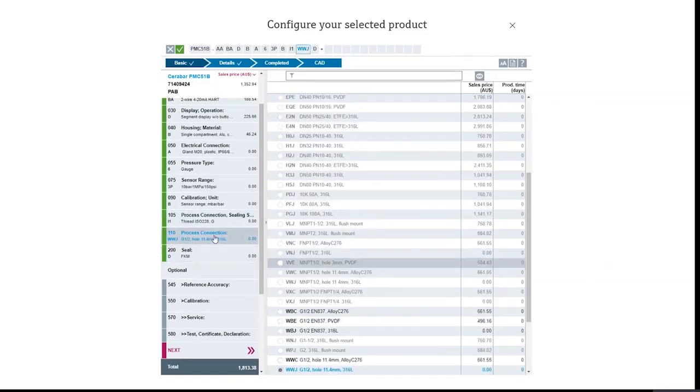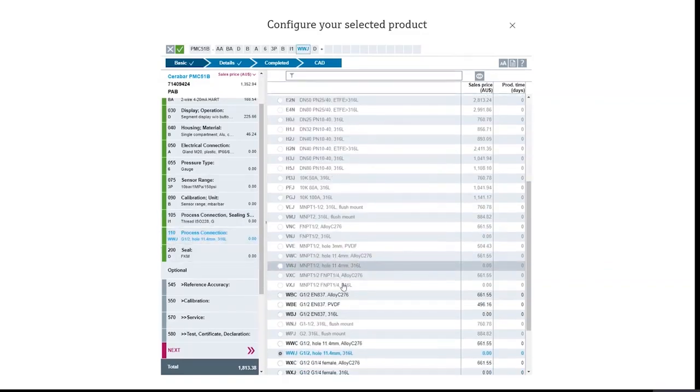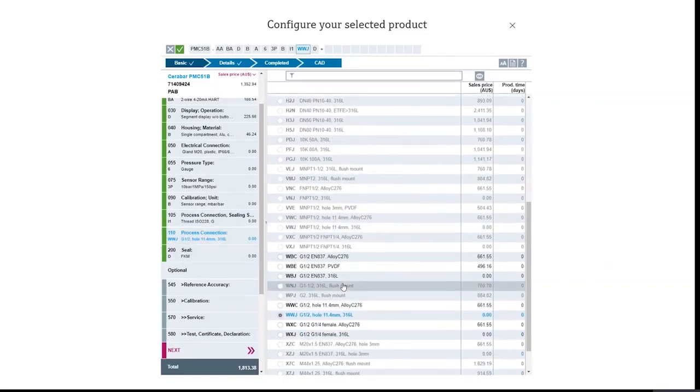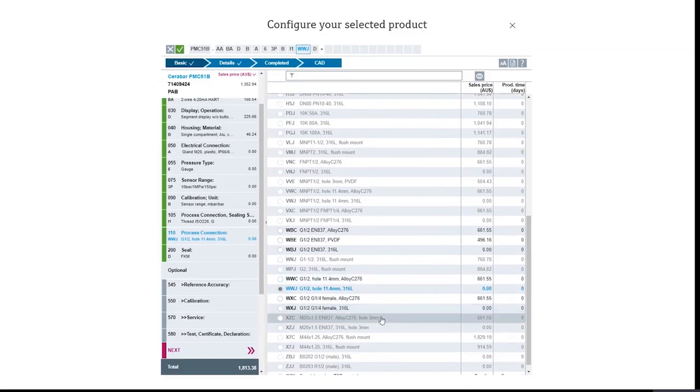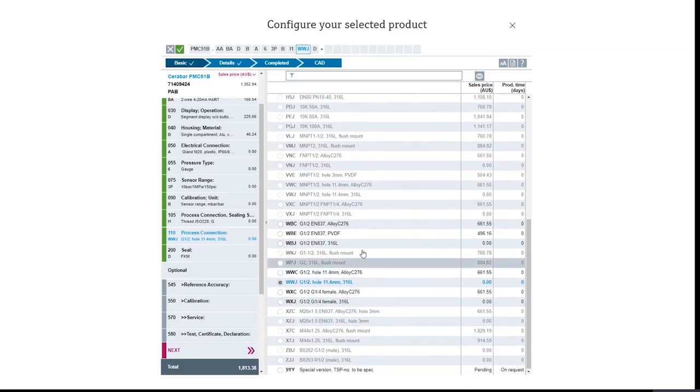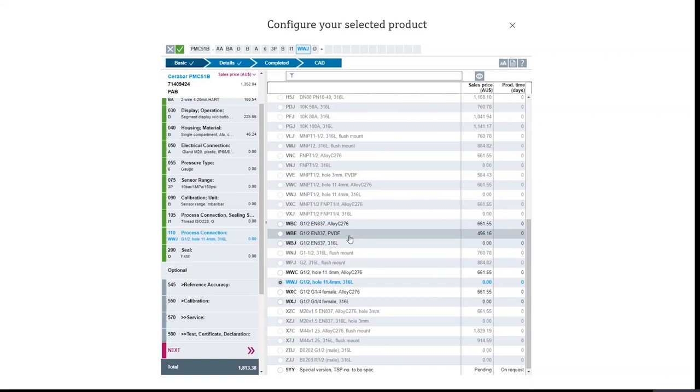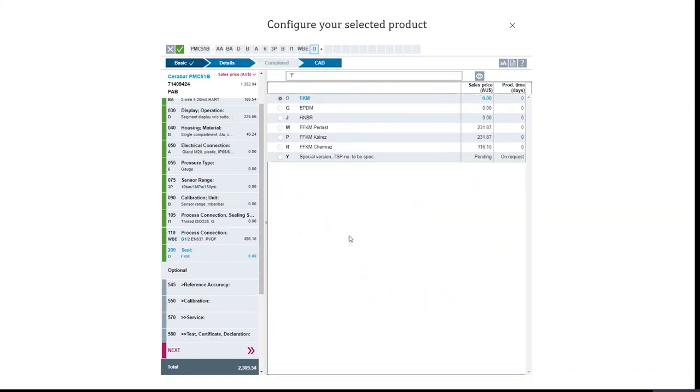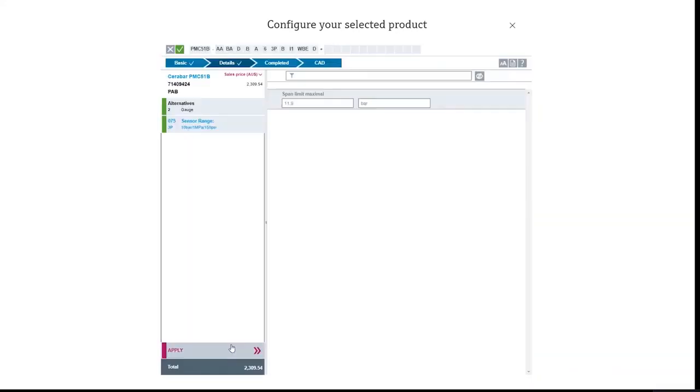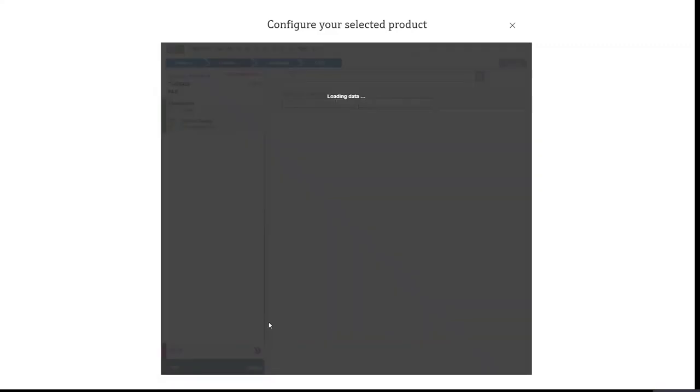So in this case, we've got half inch BSP 316 stainless. We're probably going to need PVDF. So let's instead select that. That's going to be better for our hypochlorite. Click next. Click apply. And there you go, you've changed the specification on your pressure instrument.